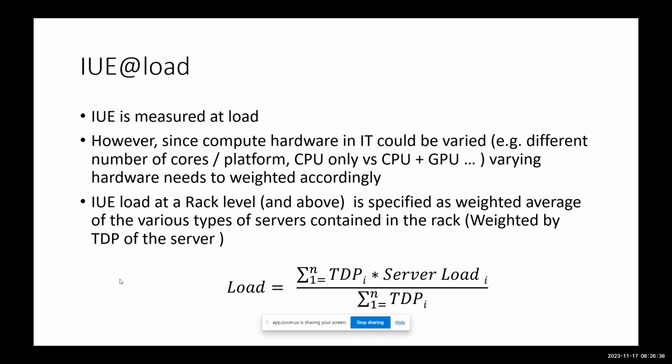So essentially, your number of, forgive me Sammy, I said servers. My pedigree, right? It could be anything. Whatever the hardware, just hardware, whatever the load is. And then each one has a thermally designed power limit, right? And then divided by the TDP is really your load on the system, right? And the reason I'm picking this, you can immediately say, well, nobody operates at TDP. Yes, but that's supposed to be the envelope, and you're below that envelope in a certain sense, and that ratio is defining your load.